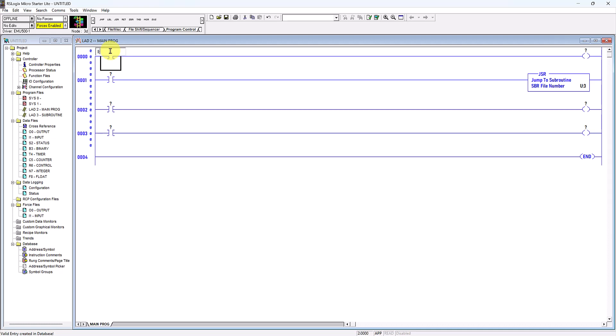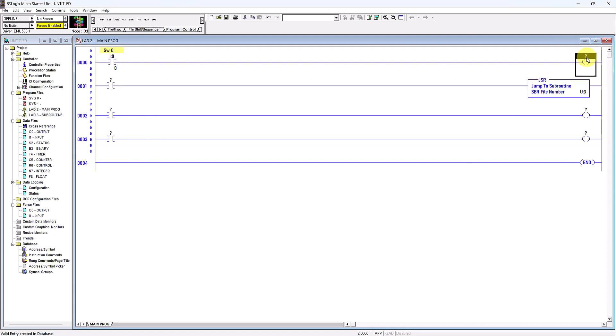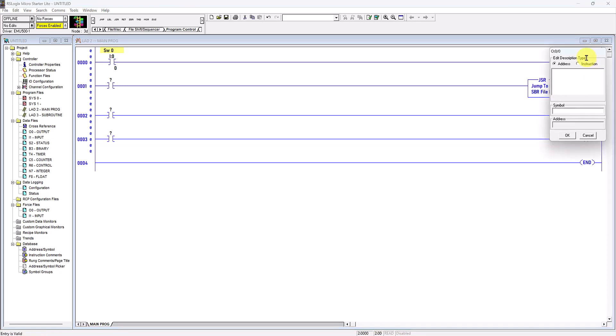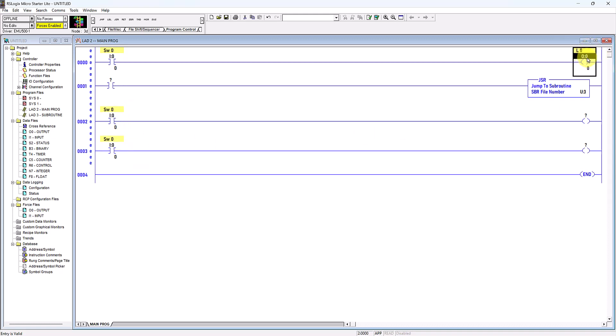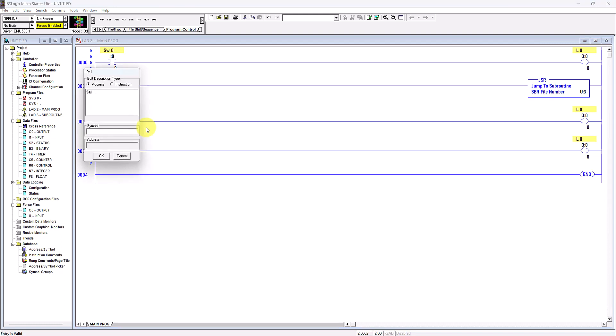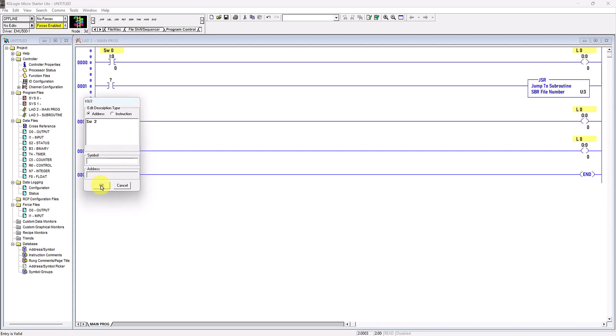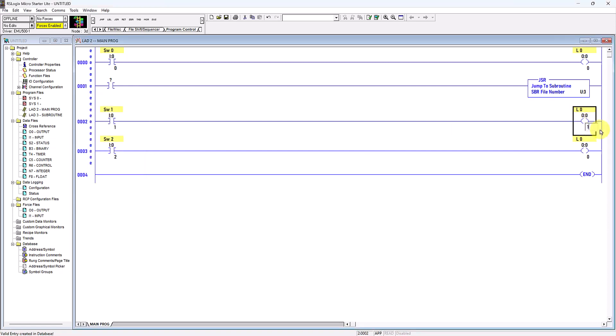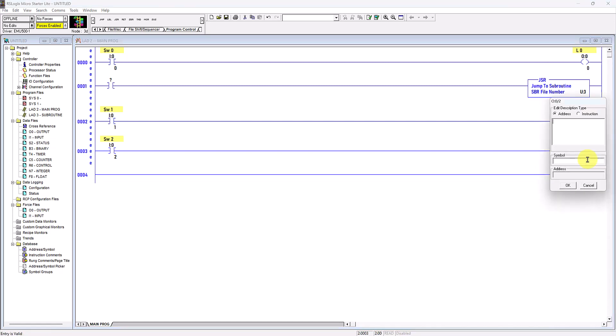Now I will write the addresses for all the instructions. This is a digital input: I:0/0 — I'll name it Switch 0. This digital output is O:0/0 — named Lamp 0. I'll copy the addresses and repeat: I:0/1 is Switch 1, I:0/2 is Switch 2, O:0/1 is Lamp 1, and O:0/2 is Lamp 2.